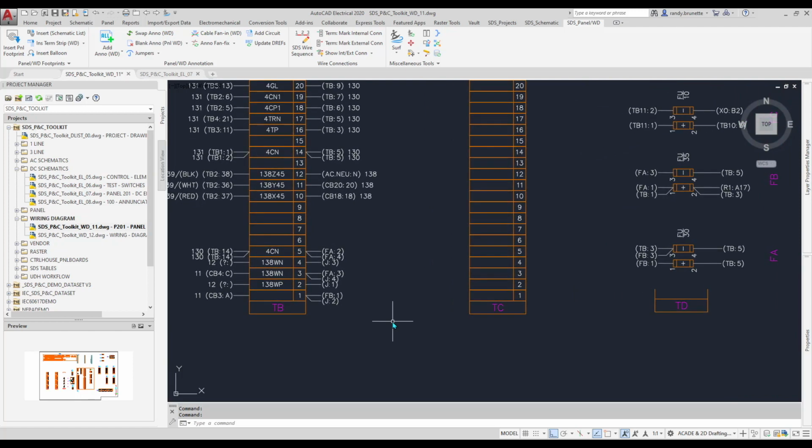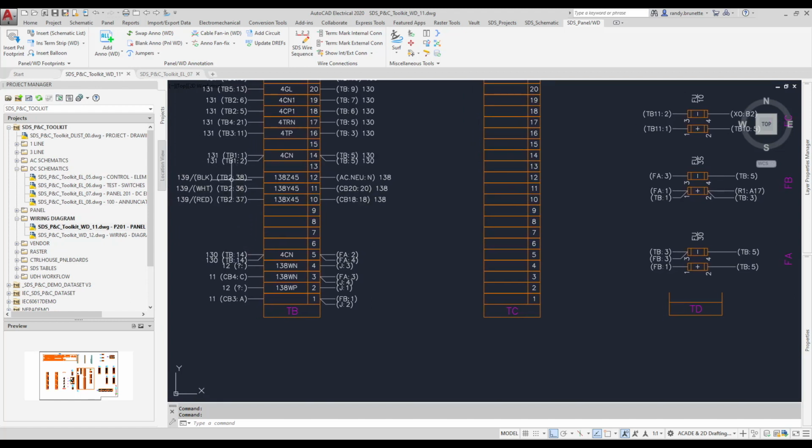We can see we have the wiring annotations coming in. Here, just to zoom over a little bit more, we can see a cable that's showing you the cable number, the color of the cable, remember that backslash, parenthesis, backslash, and here's the terminal numbers, or the component tag and the terminal number again with the parentheses. And you could see from that earlier option box how we can make the changes and define how we want that information to be placed.